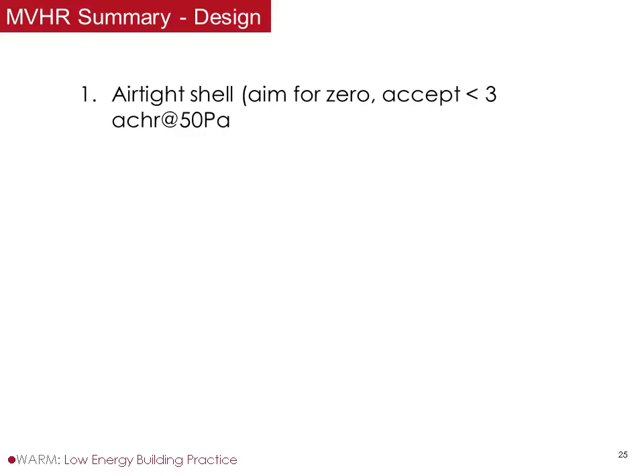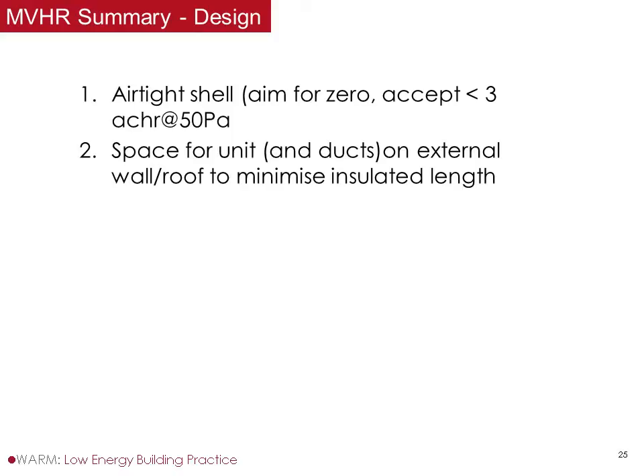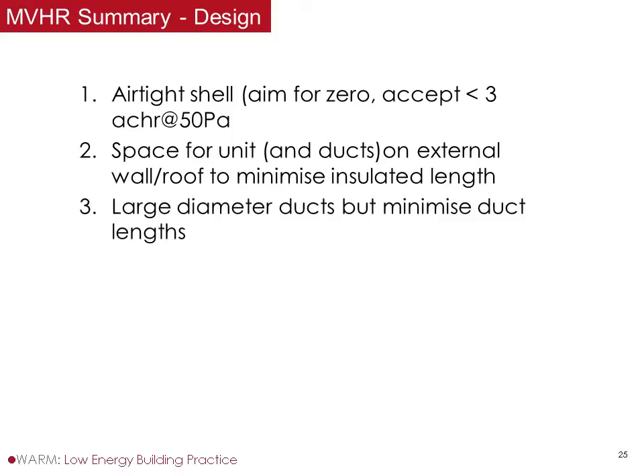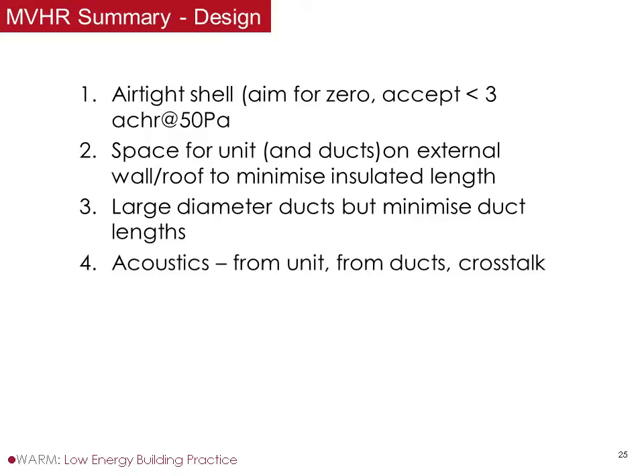Okay, so a quick summary on design. We've got an airtight shell — you must have an airtight shell if you're going to go for balanced mechanical ventilation. Aim for zero, but certainly less than 3. You need a space for the unit and the ducts on an external wall to minimise the insulated length, and you need large ducts, but you need to minimise them. Acoustics are important too, designed in terms of attenuators from the unit, the ducts, and crosstalk.